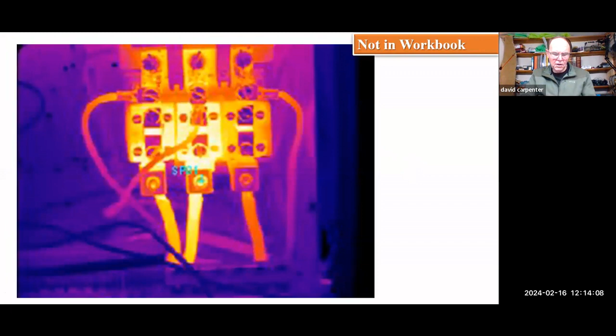Is there a website or way to get an Excel spreadsheet with all the calculations required for an arc flash study? You normally buy software for that. However, if you go to NFPA 70E, there are some basic calculations for basic operations. You may have other instances that change the calculation, but yeah, they're there. The formulas are found in the annex - you can see the formulas used for doing arc flash calculations.